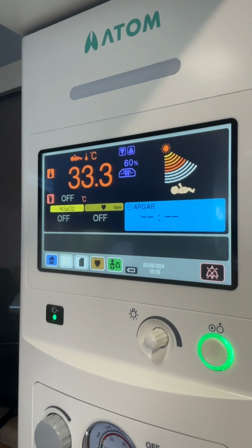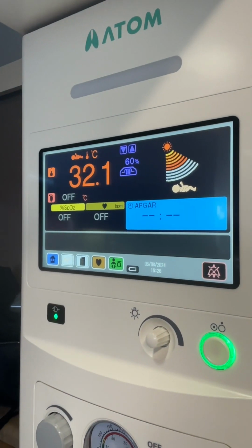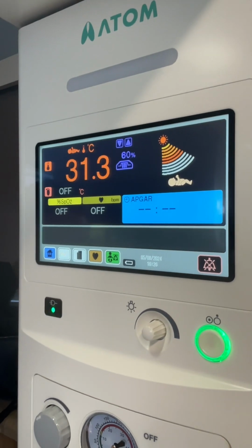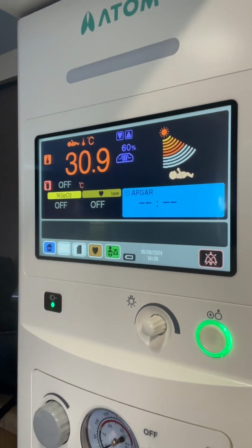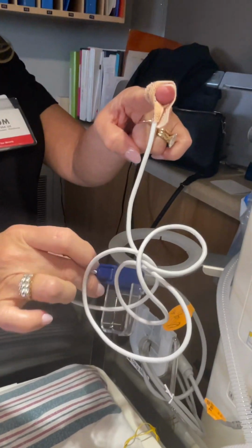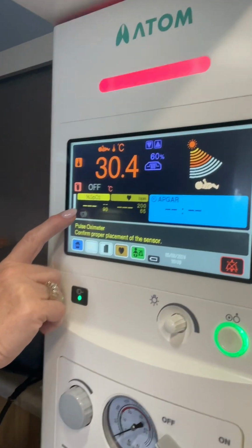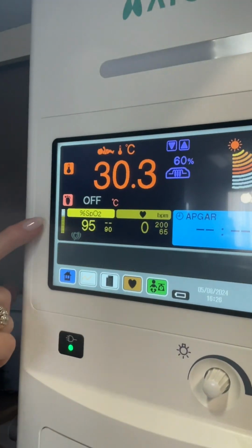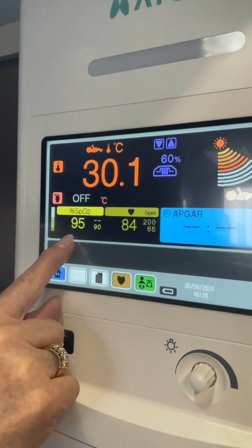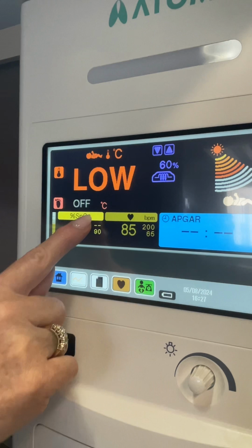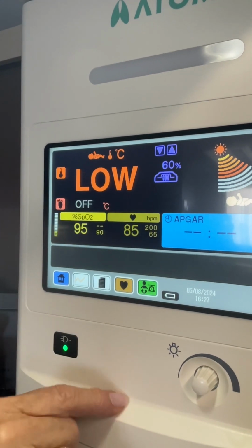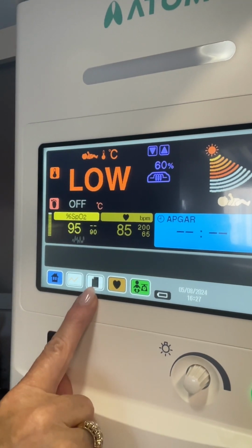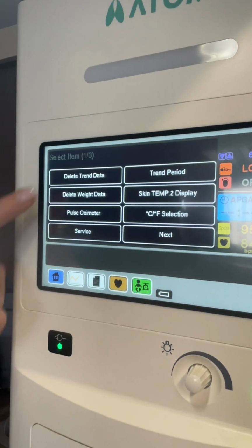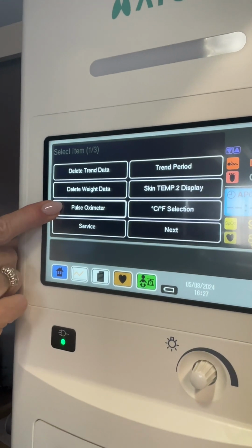This one has built-in pulse oximetry. So once the pulse ox is on your baby, all you have to do is connect the sensor to the cord. And once you connect the sensor to the cord, it'll turn on your oxygen saturation and heart rate, your pulse oximeter in other words. So oxygen saturation and heart rate, the numbers to the side are your high and low alarm limits. If I'm looking at the menu bar, the third item, this little page, if I select that, the third item here is pulse oximeter.